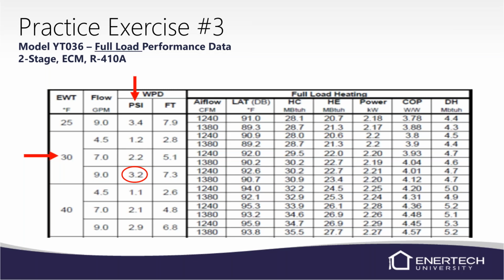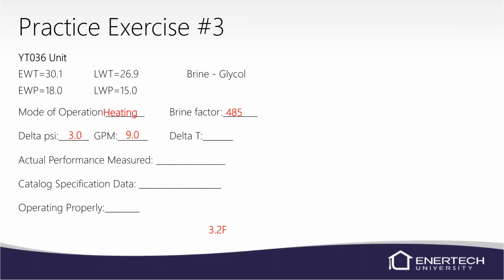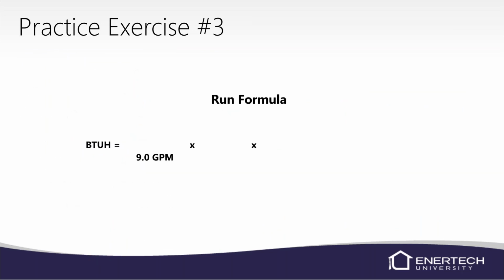But we saw that 3.2, so you're still starting to think in your mind, 3.2 seems kind of low on our temperature difference. So we'll go ahead and run the calculation. 9 GPM, delta T of 3.2. So we run 9 GPM times our 3.2 times our brine factor of 485. And that gives us 13,968 BTUs.